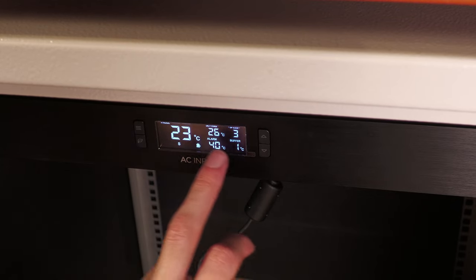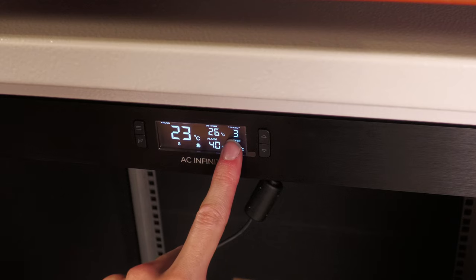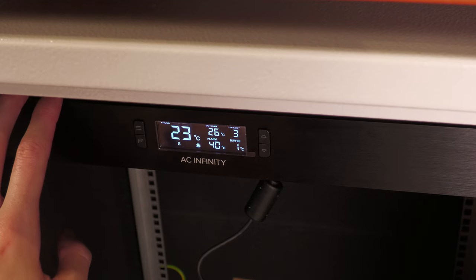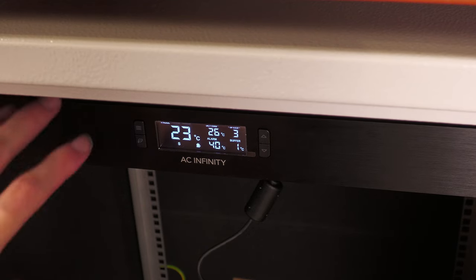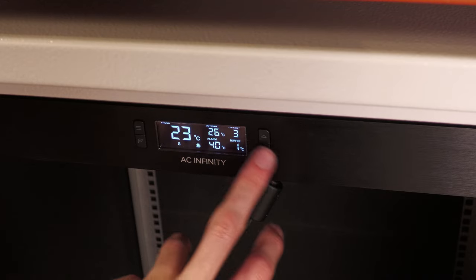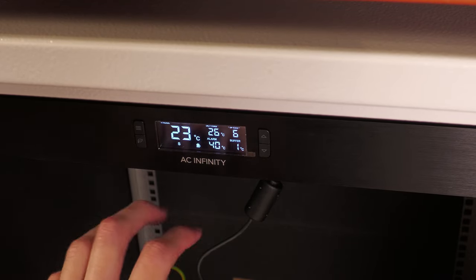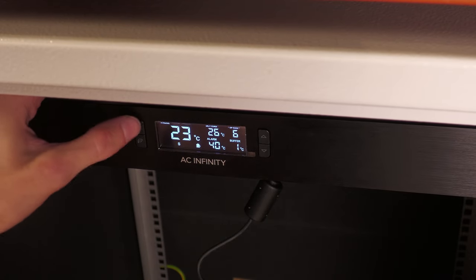So if you use a speed mode, you can either set a fixed speed, or it sets a speed limit for smart mode, or sets the actual speed the thermostat mode will operate at. So I can leave that on 6, but you can change that. And it's nice to have that ability to limit the speed.